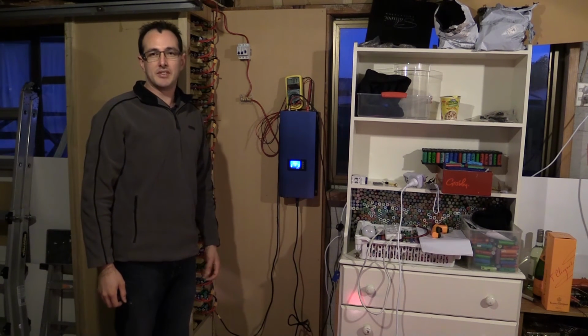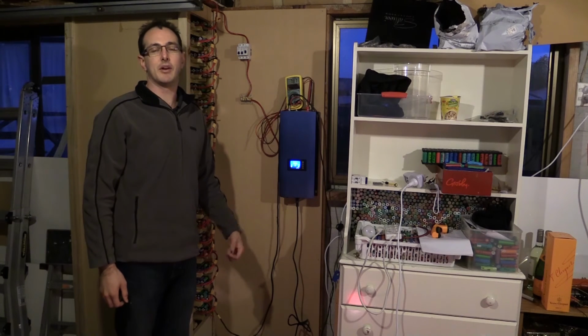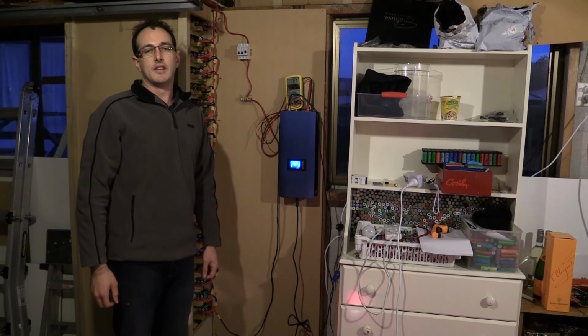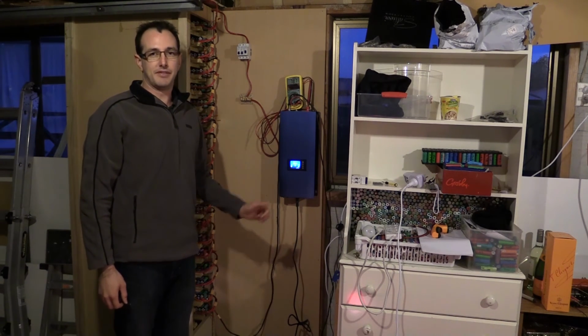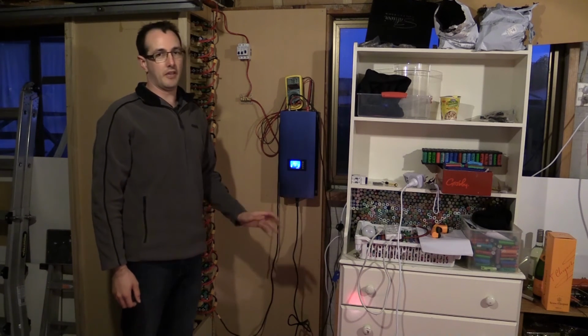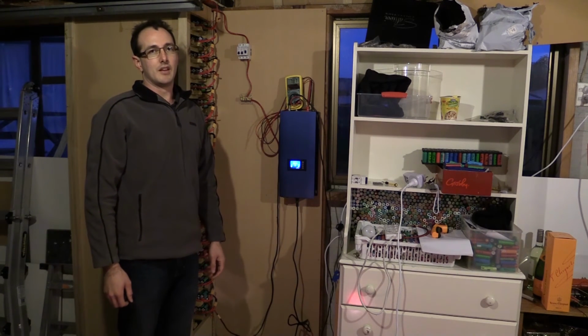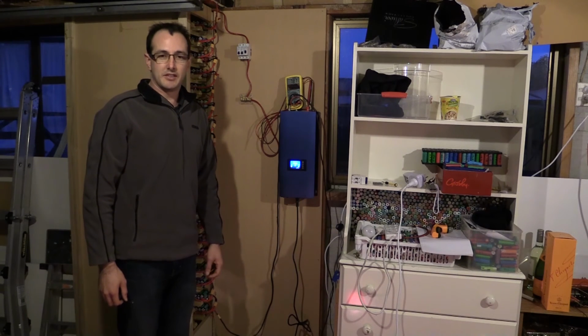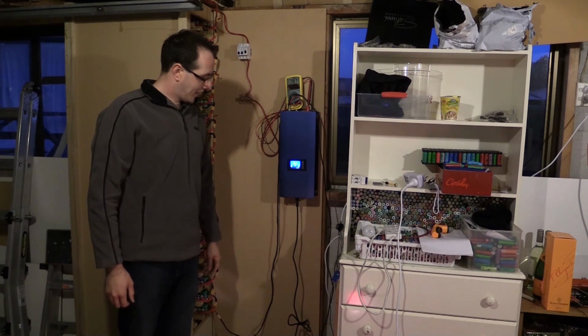So the way I had it set up before was I had the CT clamp around the load. Now what I've got is the CT clamp before the inverter and before the load. In other words, higher up the food chain. So that's really good. That's fixed our problem.